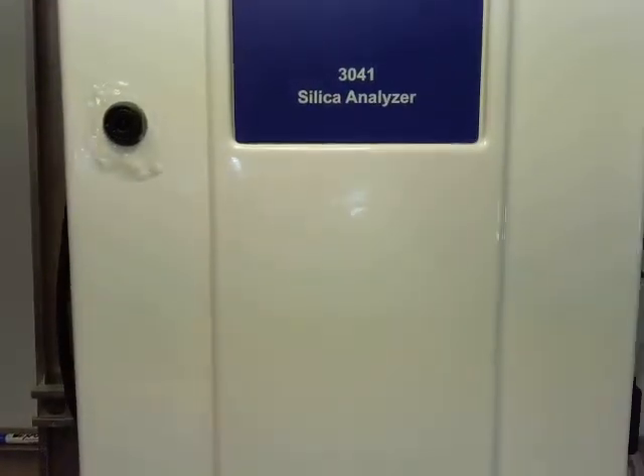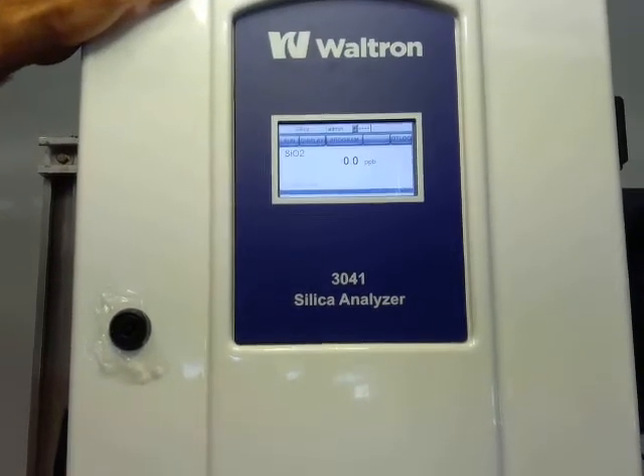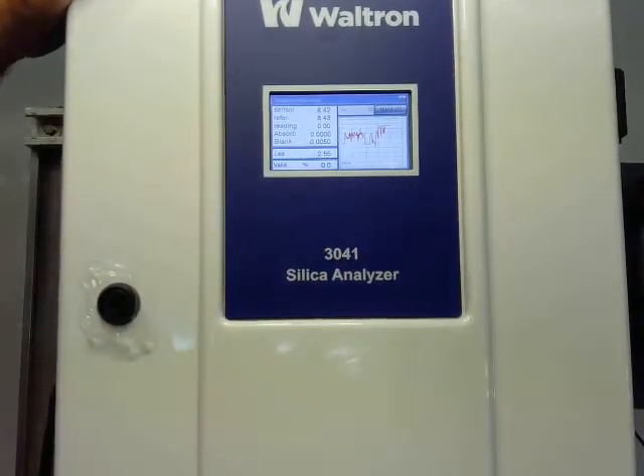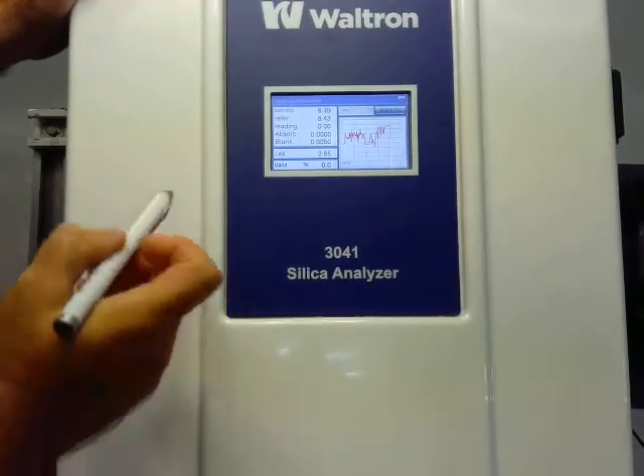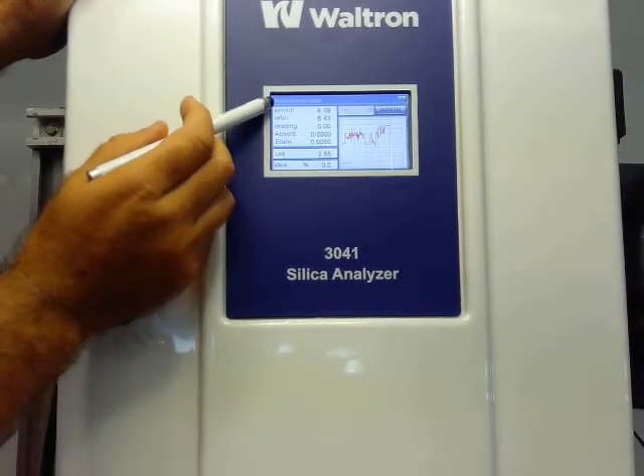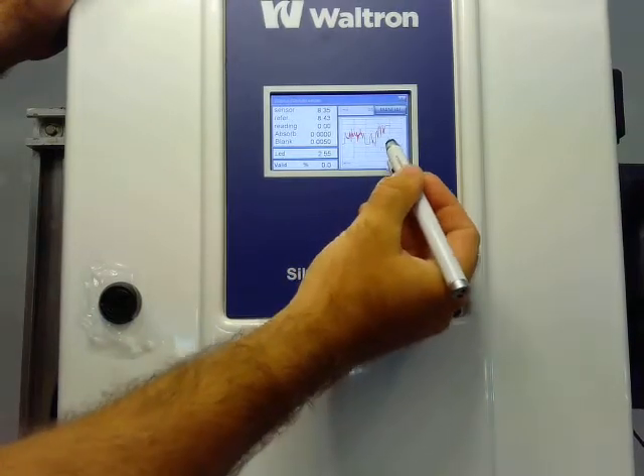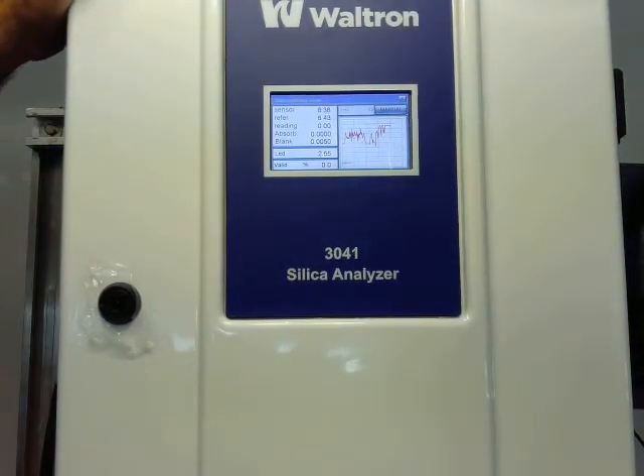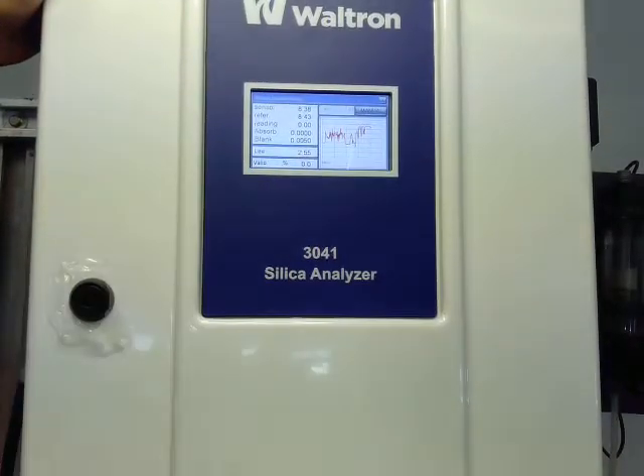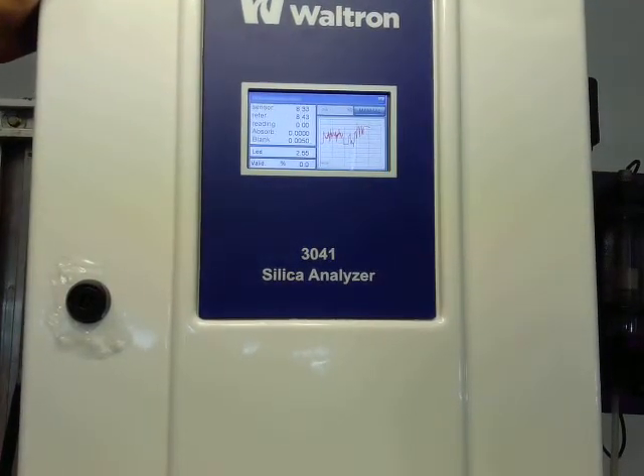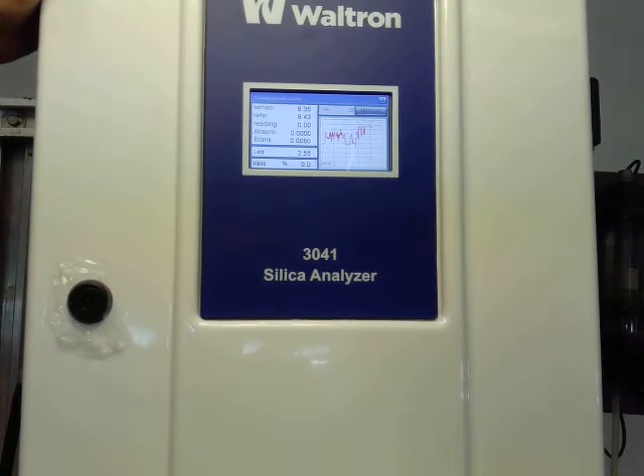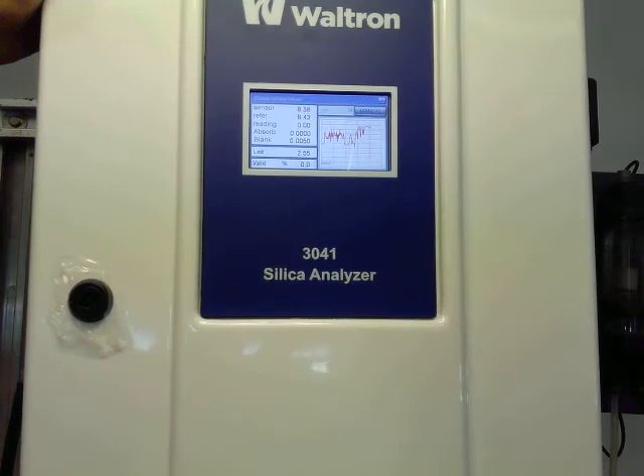And we'll take a look back at our menu screen to see from our display menu what's going on here. So again, the sensor value is the only number right now that's moving around. And this graph is just plotting that sensor value as things happen. These big spikes here are our sample flow cell filling and emptying. When it empties, that number goes way down because it only has air in the cell, and then as it fills up with sample, it should be around 8.5 or 9.